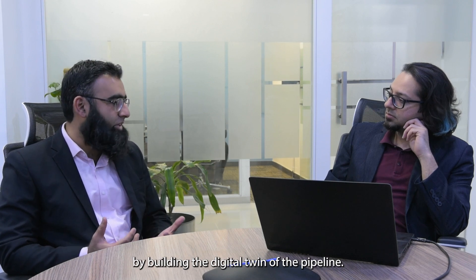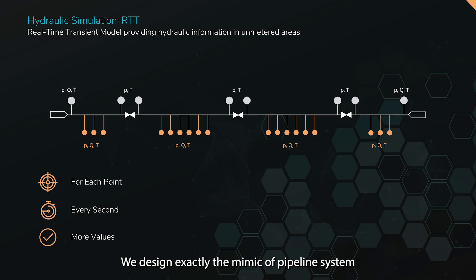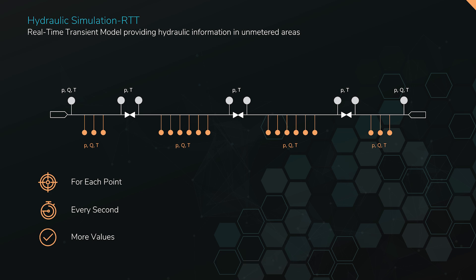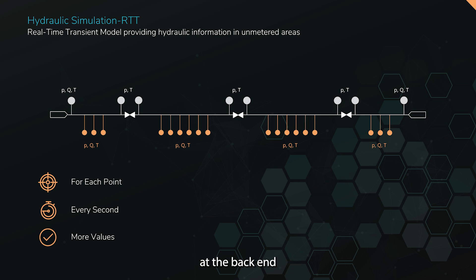How exactly does software-based leak detection work? We start configuration by building the digital twin of the pipeline. We define the mimic of the pipeline in the system by specifying characteristics such as diameter, length, elevation profile, roughness, and thickness. All these parameters are configured inside the software to create the digital twin. Once the twin is ready, the software starts the simulation and performs calculations in the backend based on the laws of conservation of mass, energy, and momentum.